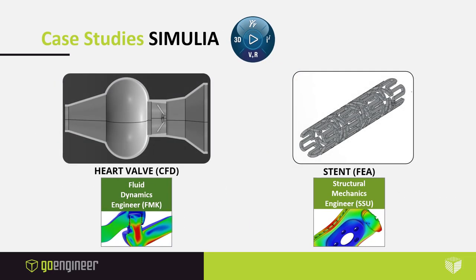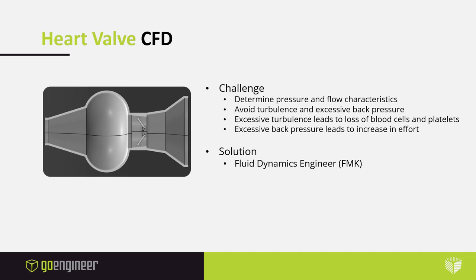To showcase the technology, we've set up two case studies: a CFD of a heart valve and a structural analysis of stent deployment. The heart valve test apparatus is a simple device with a very big effect on justifying the efficacy of the heart valve design. The primary goal is to determine the pressure and flow characteristics of blood through the heart valve — specifically avoiding turbulence, which leads to killing blood cells and platelets, and excessive back pressure, which forces the heart to work harder to transport blood across it.